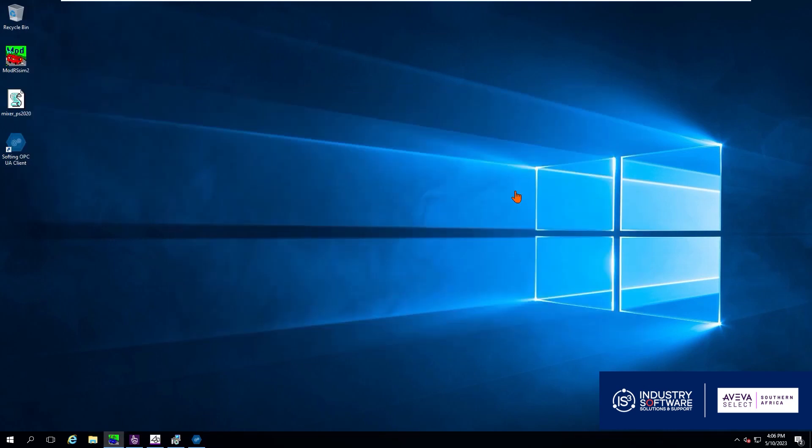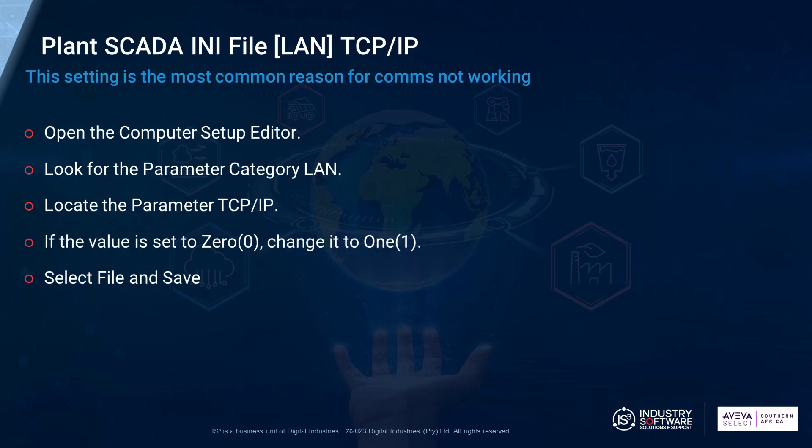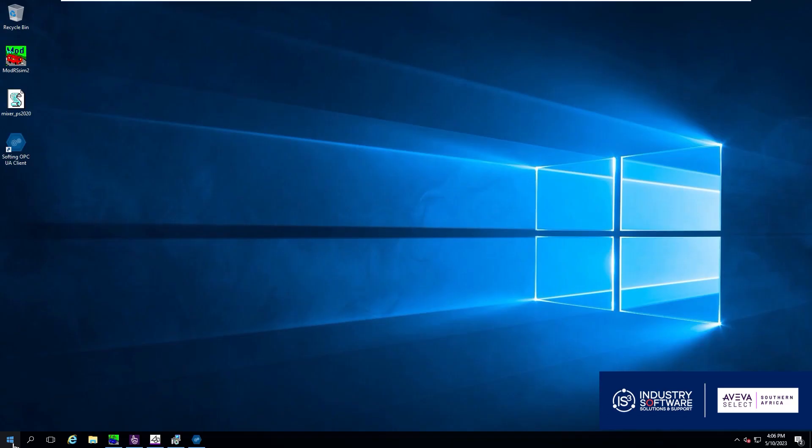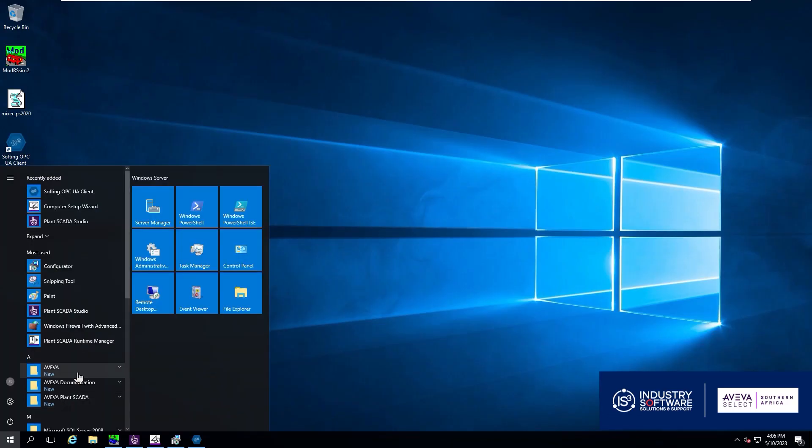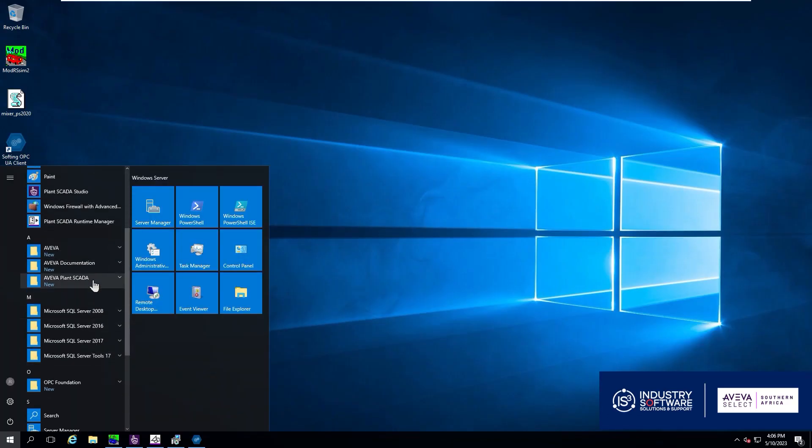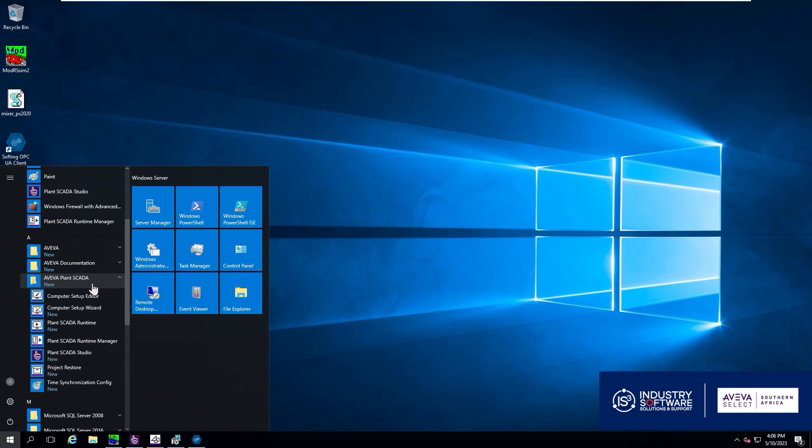Next up is the TCP IP parameter in the INI file and we will now go check if this is a zero or one value. Even if it is an all-in-one node it needs to be set to one so that the SCADA data can be seen.